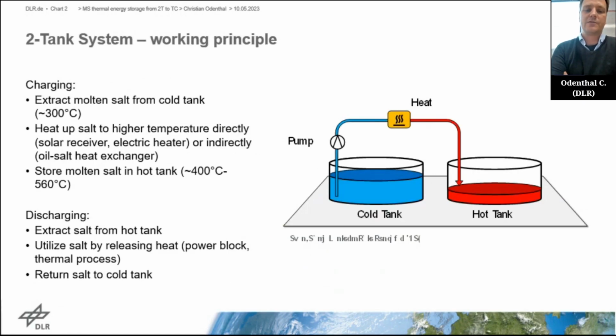So regarding the two tank system, I think most of you are aware of its existence, and I think the working principle is also quite simple. You have two tanks. They are filled with molten salt. Typically, the so-called cold tank has a temperature of about 300 degrees Celsius, and that salt is extracted from that tank and heated up to a higher temperature. That can be, or typically is done in concentrating solar power plants. But that can also be in newer fields of application. For example, an electric heater. Thomas will later show some examples in his presentation about that topic.